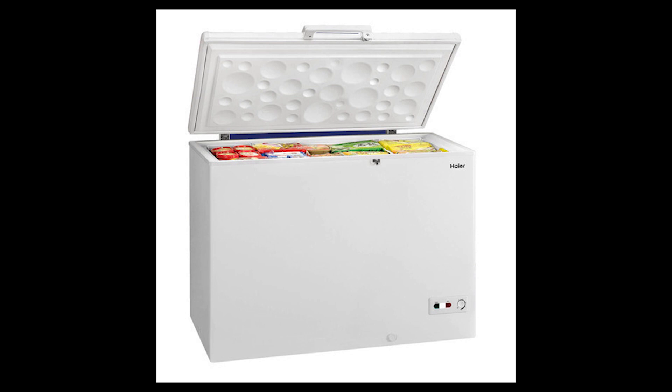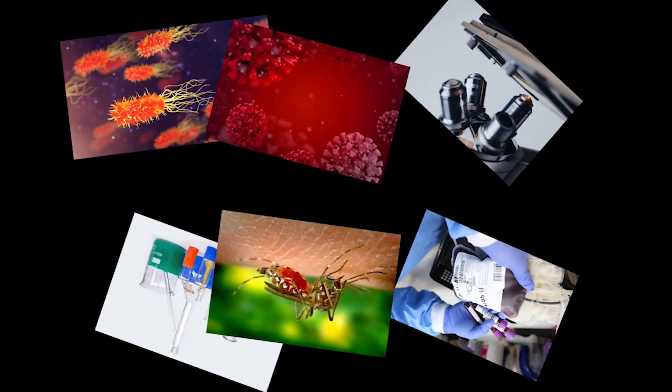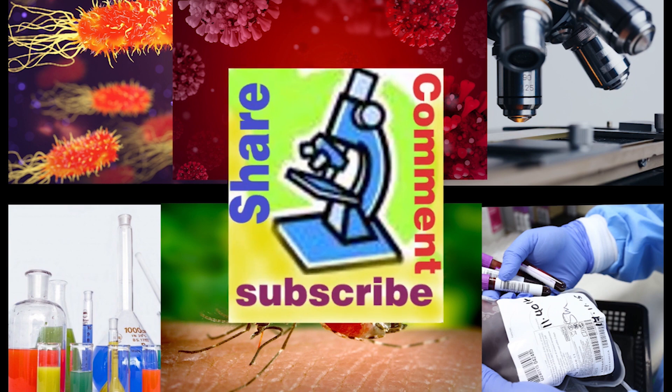To get good QC results at the first run requires a lot of preparation and time. Do not run QC with faulty instruments, reagents, calibrators, and QC materials, as that can consume a lot of time and expensive reagents, calibration, and QC materials. We will have another video about the reasons for calibration failures and QC failures. Please do write your comments to make more videos.